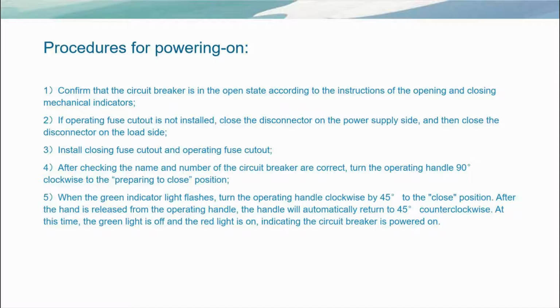4. After checking the name and number of the circuit breaker are correct, turn the operating handle 90 degrees clockwise to the preparing to close position. 5. When the green indicator light flashes, turn the operating handle clockwise by 45 degrees to the close position. After the hand is released from the operating handle, the handle will automatically return to 45 degrees counterclockwise. At this time, the green light is off and the red light is on, indicating the circuit breaker is powered on.